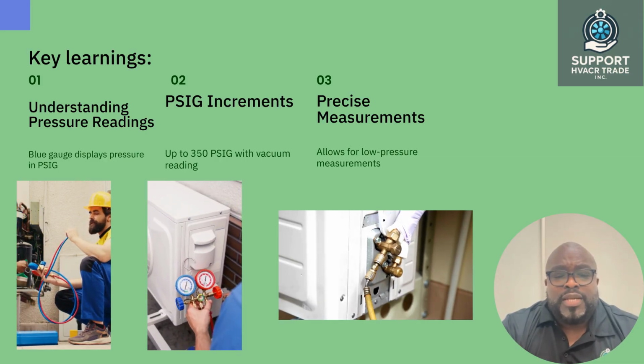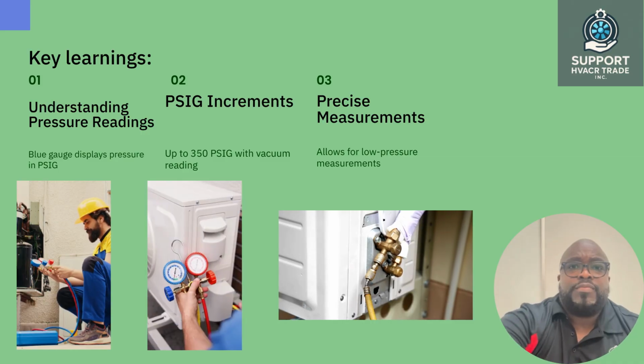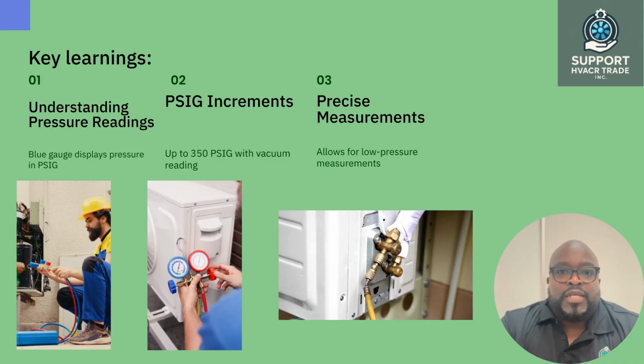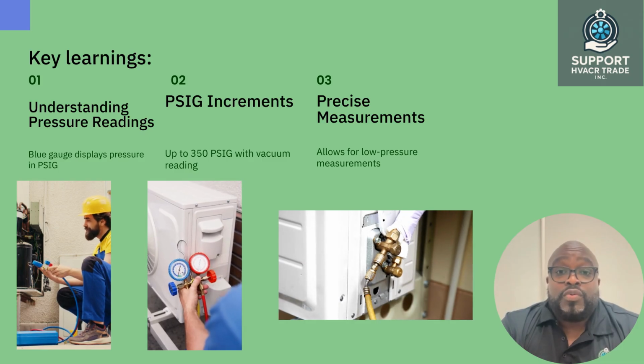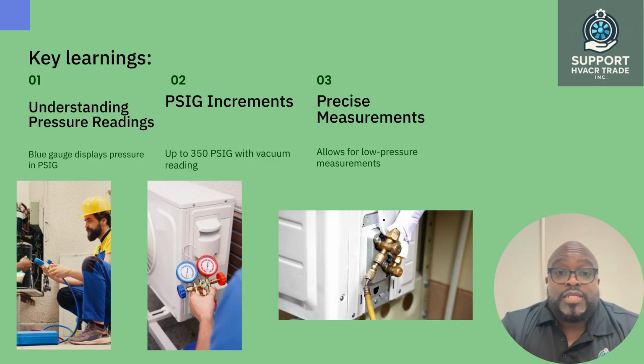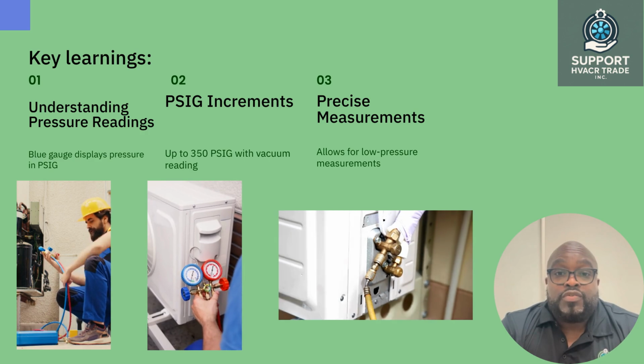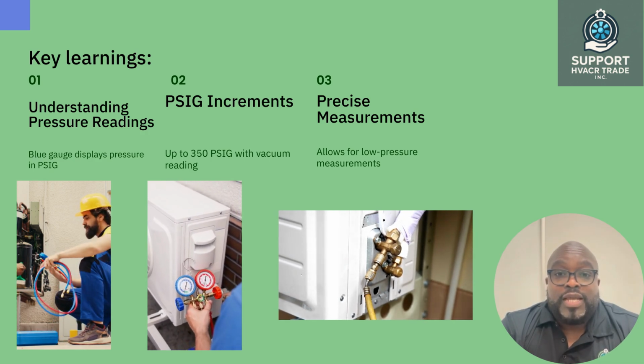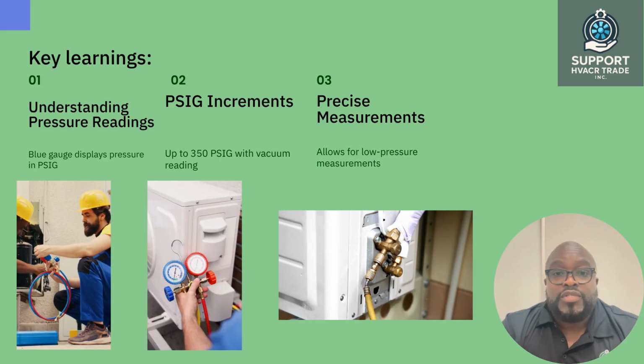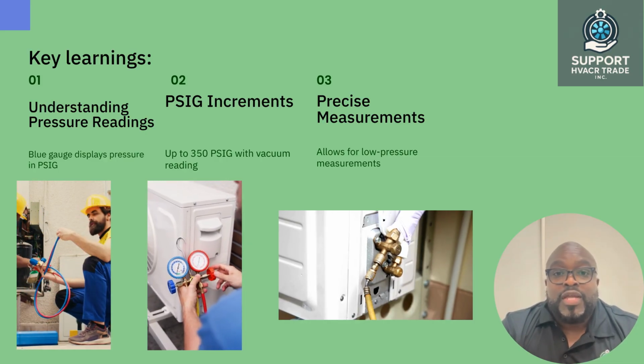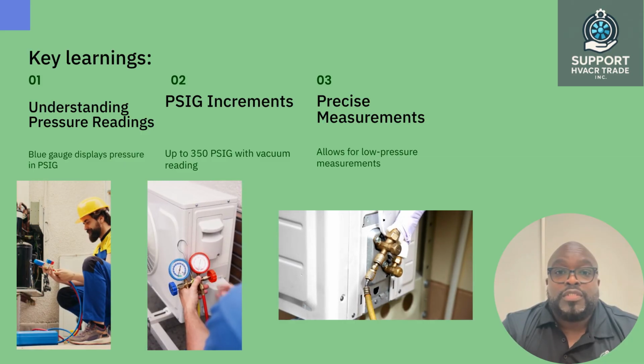Attach to the system. Connect the other end of the red hose to the high-pressure service port on the system and the blue hose to the low-pressure service port. Open the valves. Once connected, gently open the valves on the manifold gauge to allow refrigerant to flow to the gauges. By following these steps, you will ensure a proper connection that allows for accurate pressure readings during diagnostics.